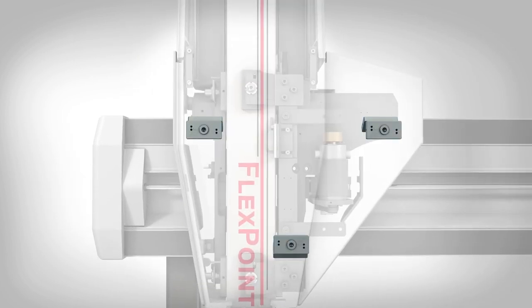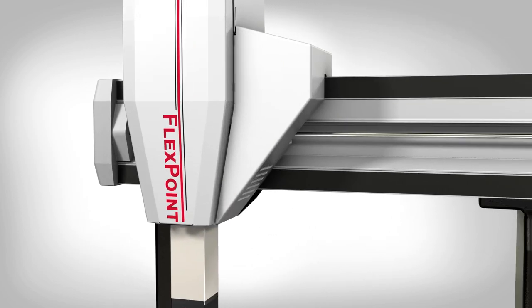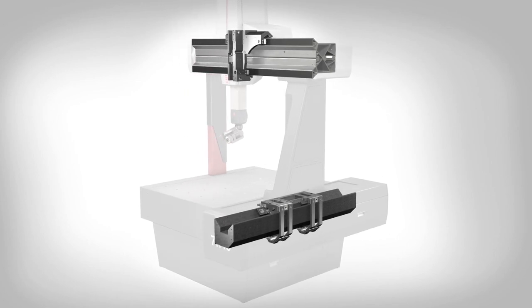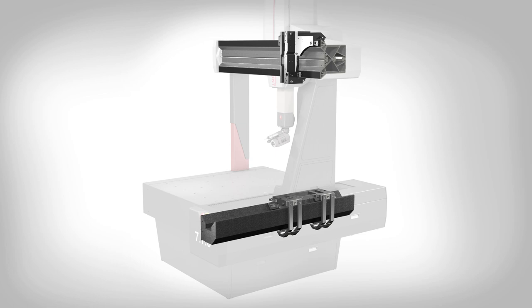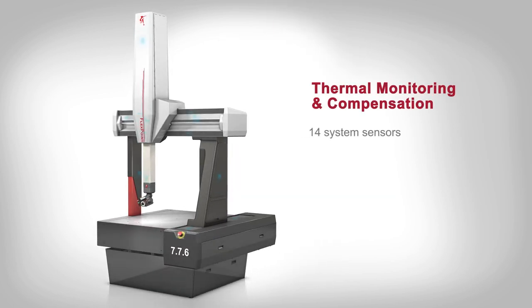The unique offset air bearing arrangement provides exceptional stiffness while maximizing usable measuring range. The exclusive QVI friction drive system provides smooth acceleration and high reliability. Thermal monitoring and compensation is standard throughout the system.